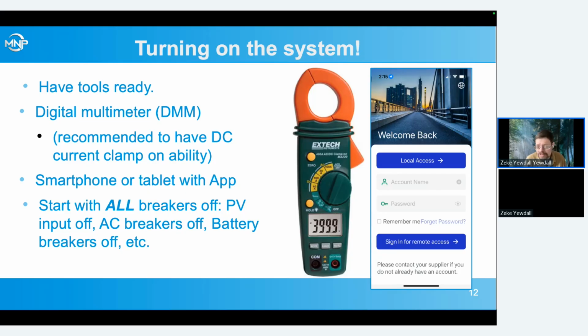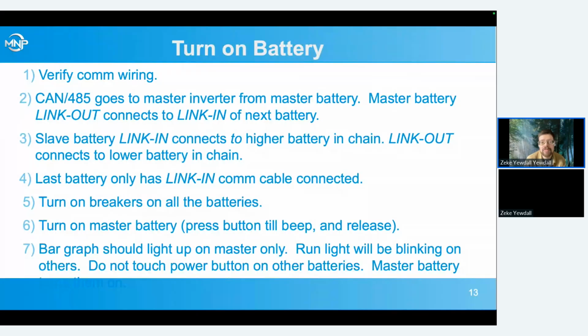Start with all of our breakers off, our PV inputs off, our AC breakers are off, our batteries are off, everything's off when we start. First thing we're going to do is turn on the battery. We want to verify our COM wiring. We've got kind of two different levels here. One is the link between our different batteries if we have multiple batteries. And then the other one is our CAN bus going between the master battery to the master inverter.